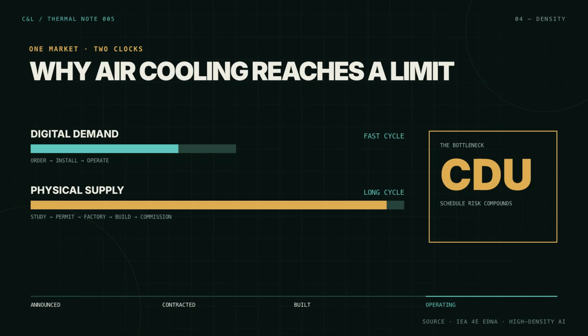Air is convenient, familiar, and easy to distribute, but it carries far less heat than liquid for a given volume. As rack power density rises, fans consume more energy and moving enough air becomes difficult. Liquid can take heat closer to the source and move it efficiently, allowing denser equipment layouts. That does not mean every data center should immerse every server. Lower density halls may remain air-cooled, and many facilities will use hybrid systems. The commercial transition is likely to be uneven. New AI halls first, followed by selected retrofits where power density and energy savings justify the cost.